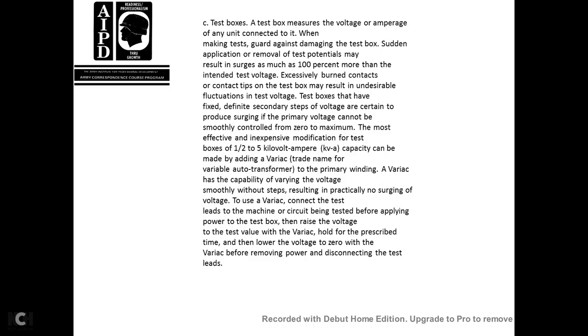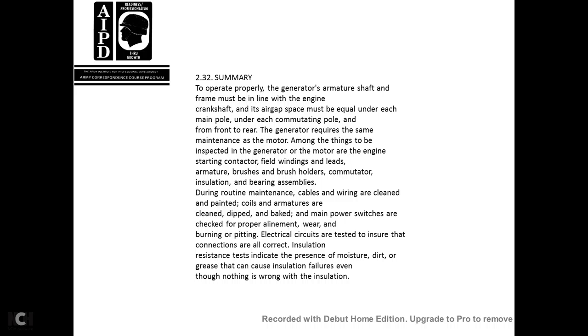The most effective and inexpensive modification for a test box of 1/2 to 5 kilovolt-amperes capacity can be made by adding a Variac, a trade name for the variable autotransformer, to the primary winding. A Variac has the capability of varying the voltage smoothly without steps, resulting in practically no surging of the voltage. To use the Variac, connect the test leads to the machine circuit to be tested before applying the power to the test box. Then raise the voltage to test value with the Variac. Hold for the prescribed time, then lower the voltage to 0 on the Variac before removing the power and disconnecting the test leads.